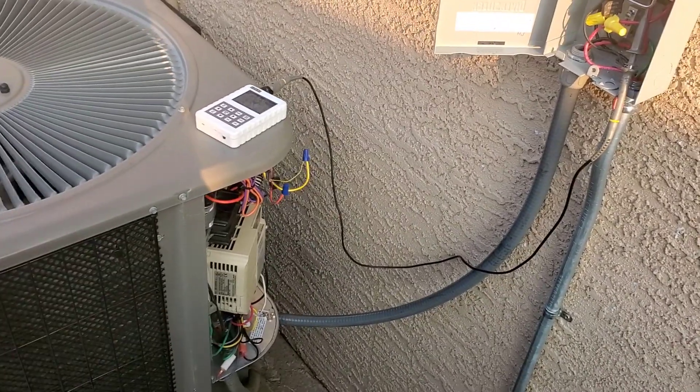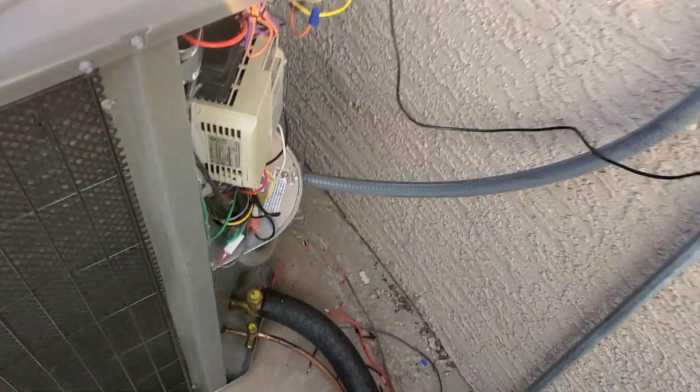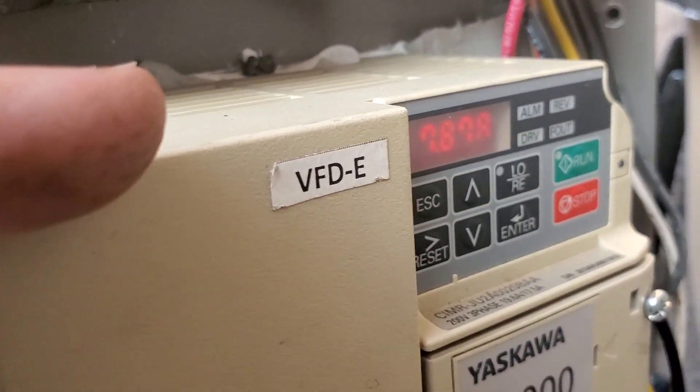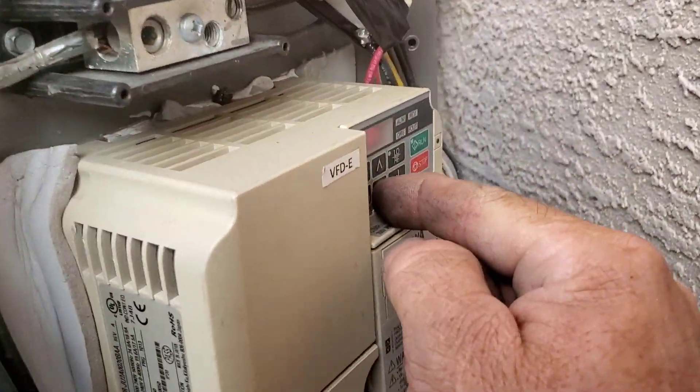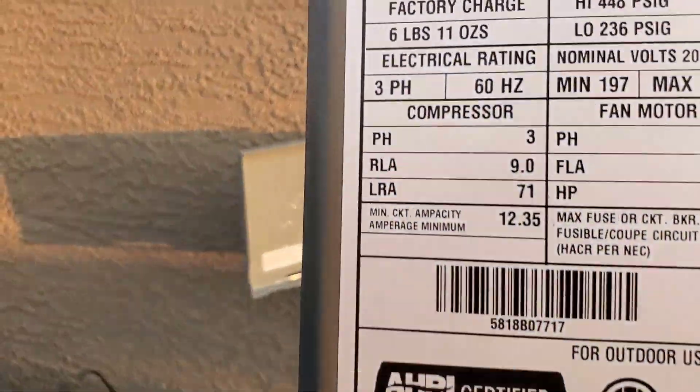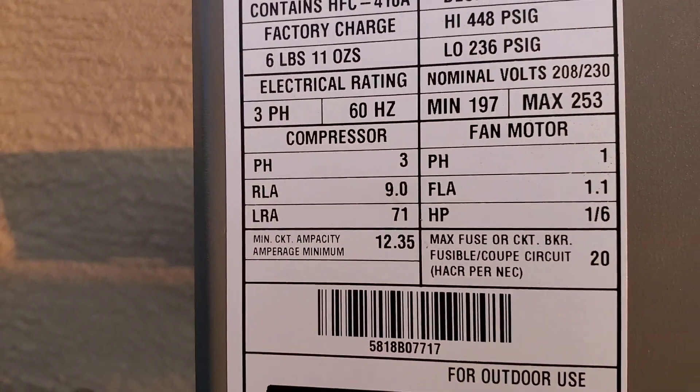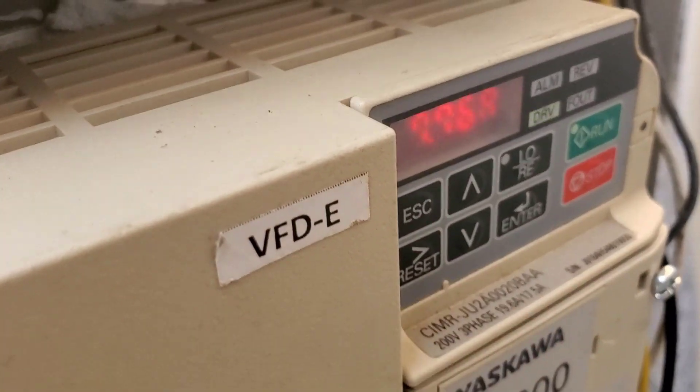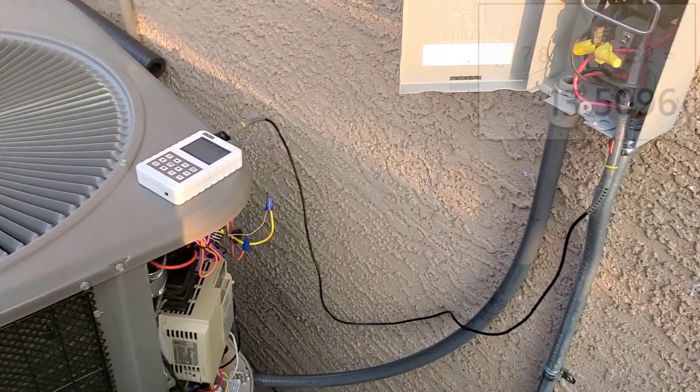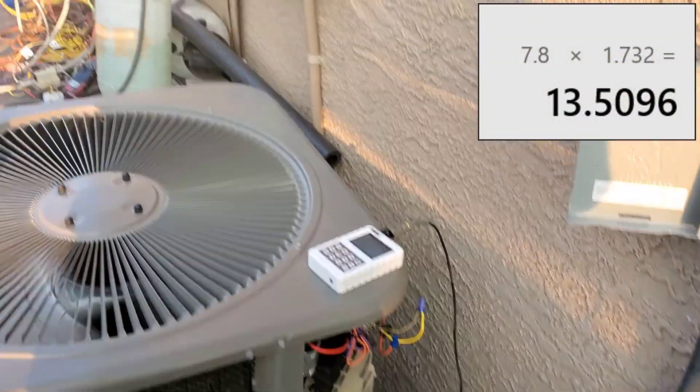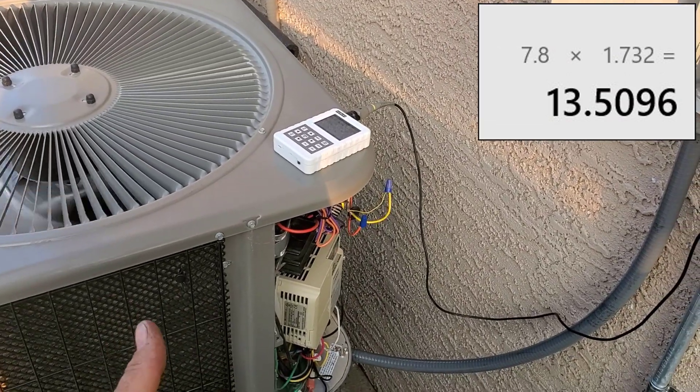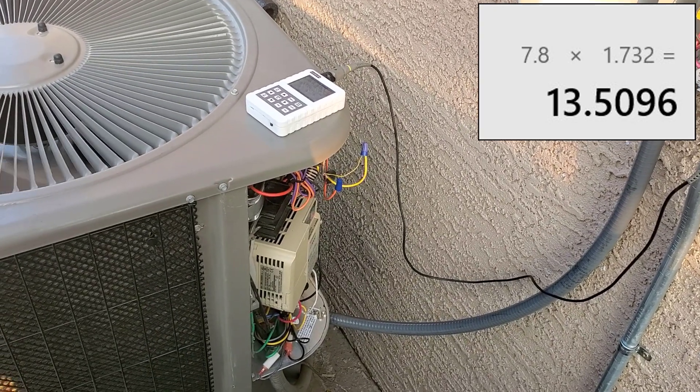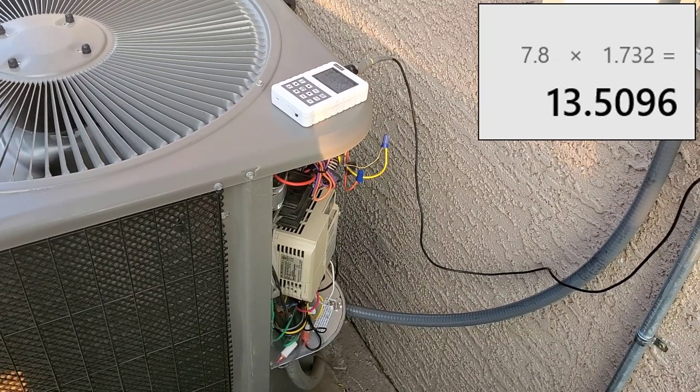The amps - like right now it's got pretty good load on this thing, hot outside - 7.8 amps. 7.8 amps is all it's running on the output at full load. The RLA is nine run load amps at three phase. And it's drawn just under eight, yeah 7.8. Basically it's probably pulling the correct power off the on-grid. It's just that my amp meter spooked me out reading 19-20 amps. Should be probably pulling like, you know, 12-13, probably at the most.